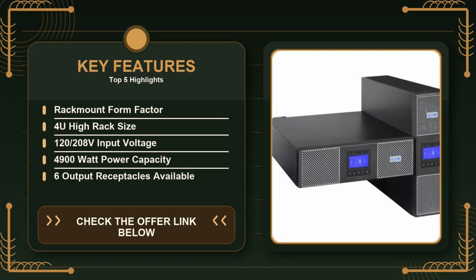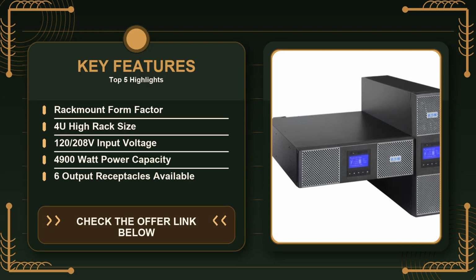First off, let's talk about what the Eaton 4900-watt, 5500 VA unit actually brings to the table. It's a 4U, rack-mountable system that can serve both 120V and 208V environments, which means it's flexible enough for most data center rows or a professional-grade home rack. The 9Ah battery means you're looking at roughly 10 minutes of runtime at half-load, a window that is short enough to give you time to orderly shut down, but long enough that you'll actually notice the difference when a brownout hits.